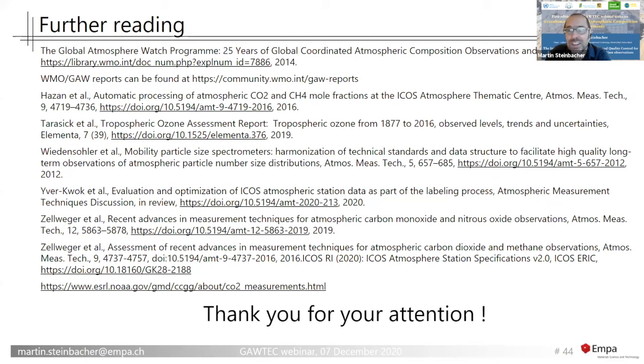And usually we suggest to start more frequently, and then after a couple of months you see if there's no real change in the instrument sensitivity. In a perfect world, the instrument sensitivity does not change at all, and then you do not need to calibrate. But for sure, it depends on changes of atmospheric pressure in the instrument, temperature in the lab, temperature in the instrument, whatever. Some dirt on the inlet filter. There are thousands of reasons why instrument sensitivity can change, and instrument sensitivity does change. And that's why usually, to be on the safe side, you do it even more often than is needed. Every couple of days, let's say.